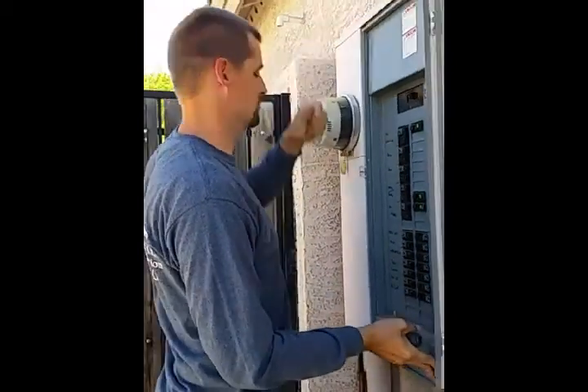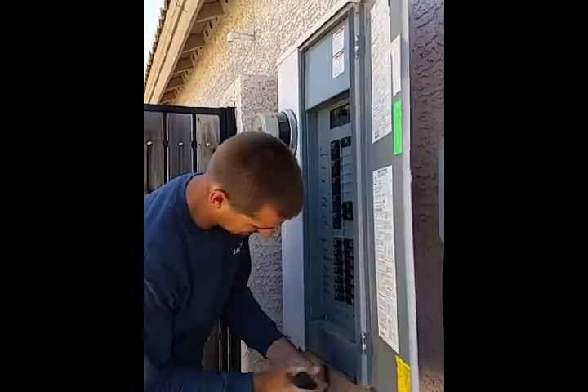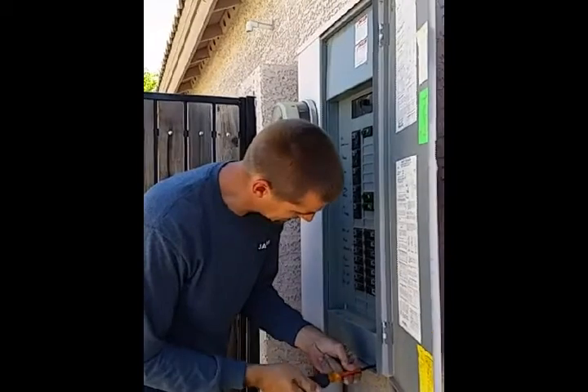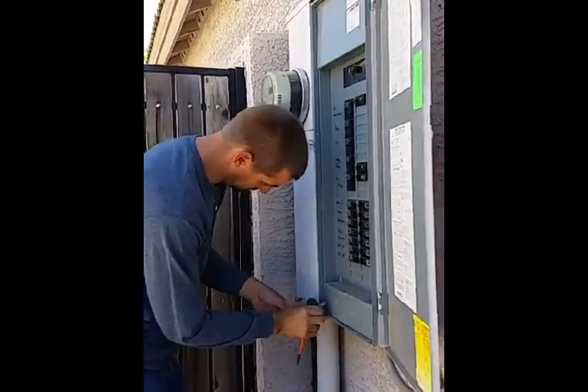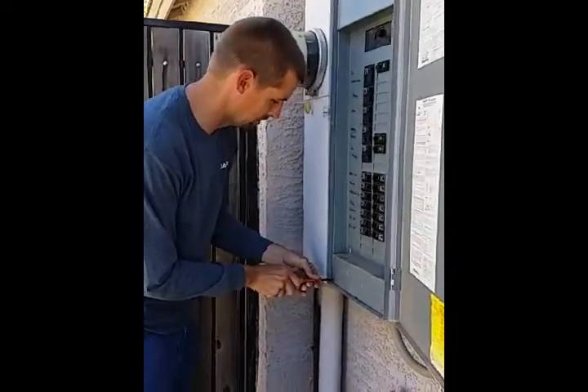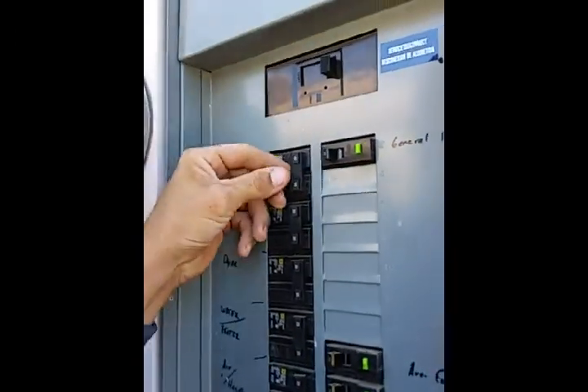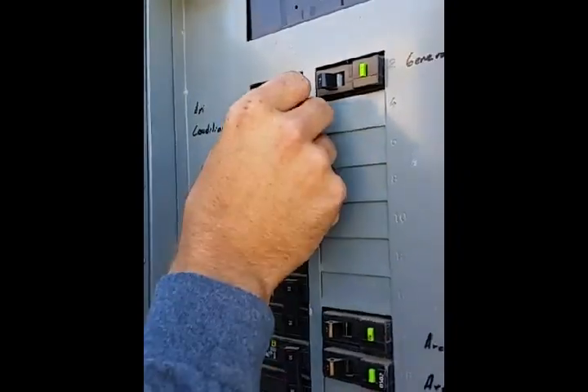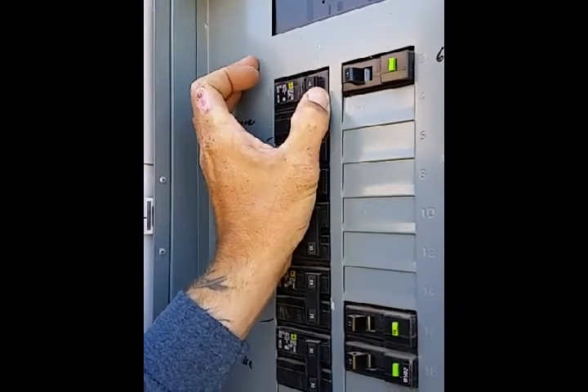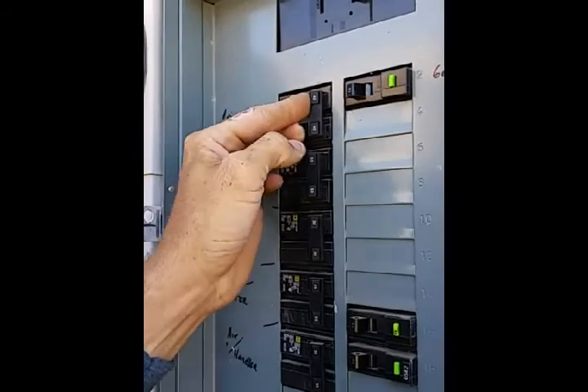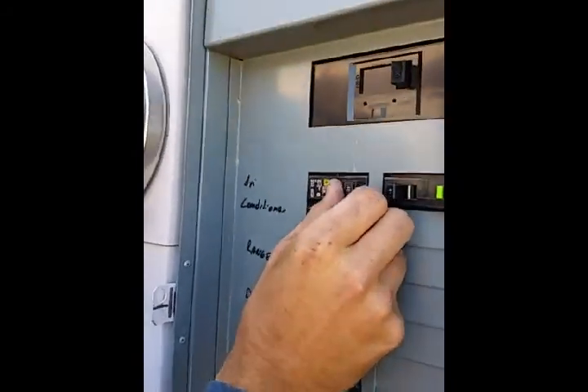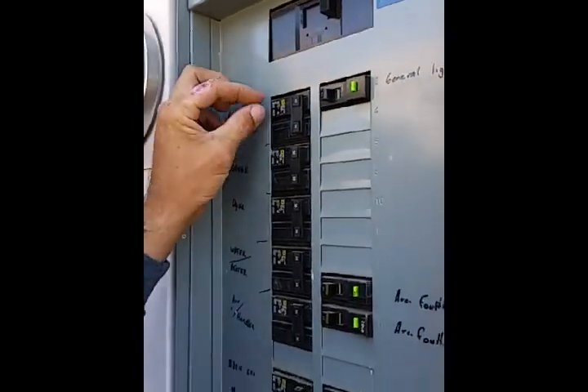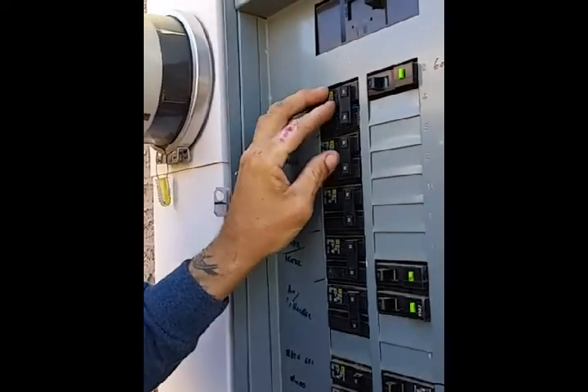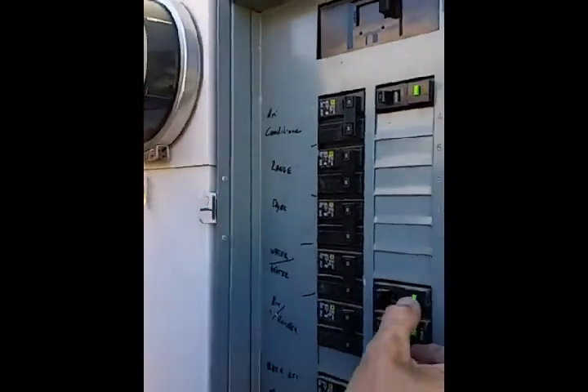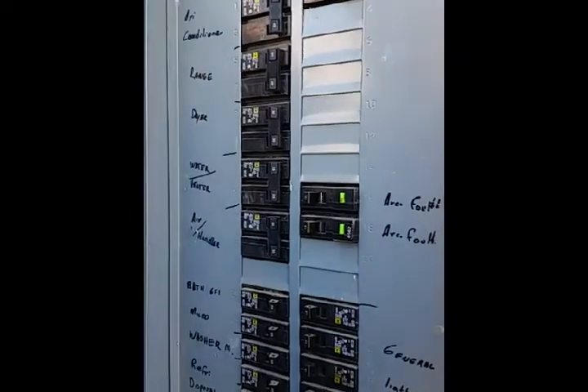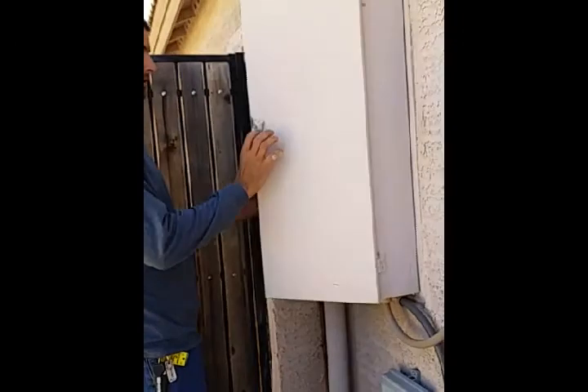Now, a lot of people don't understand what sometimes a tripped breaker is. Give me a second and I will kind of explain. Okay, now if you want to step over here, this is your breaker in the on position. Basically what happens is when it's off, it will be off. When it is on, it will be on. Tripped is somewhere towards the middle, right. Sometimes you'll have a little see-through panel here that will be red. That also means that it is tripped. Or these right here, test reset buttons. Those are tripped as well. That means that it's tripped, obviously. So there's a little bit of information as far as that goes.